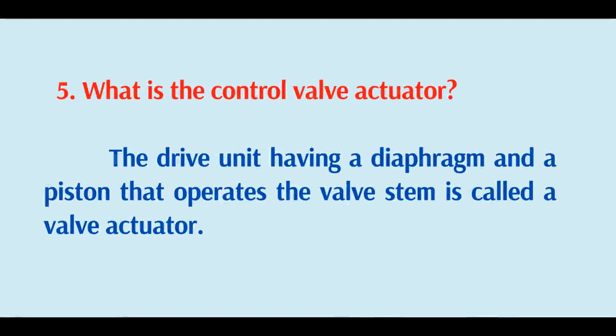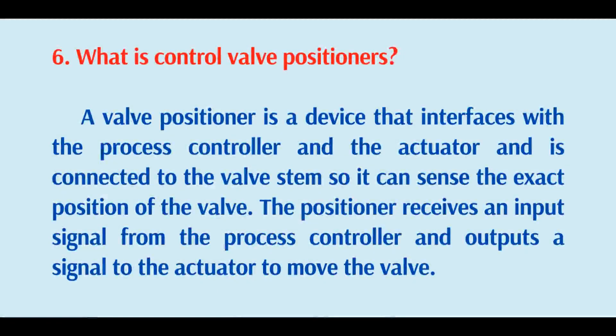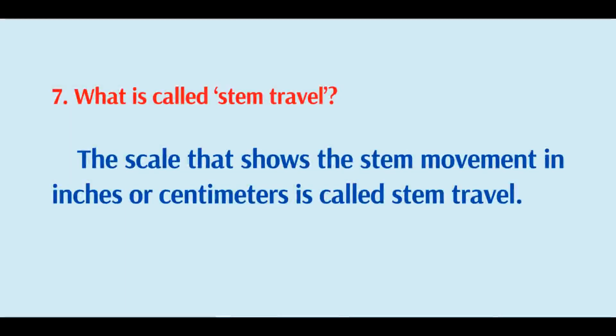What is a control valve actuator? The drive unit having a diaphragm and a piston that operates the valve stem is called the valve actuator. What is a control valve positioner? A valve positioner is a device that interfaces with the process controller and the actuator, connected to the valve stem so it can sense the exact position of the valve. The positioner receives an input signal from the process controller and outputs a signal to the actuator to move the valve.